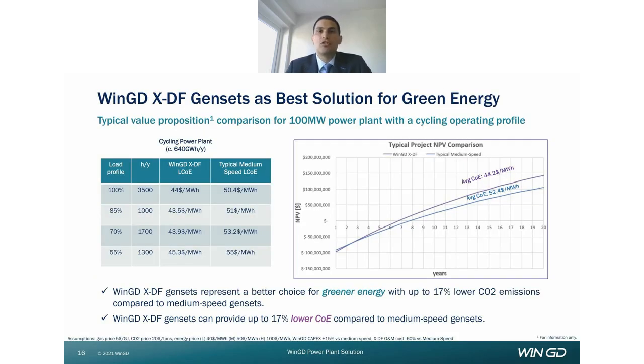I would like to conclude now my presentation with a typical value proposition, comparing 2 power plants with the same size, let's say 100 megawatt. One power plant is equipped with our XDF genset, and the similar power plant in size is equipped with a medium speed genset. The advantages that I highlighted before, the high efficiency, the low maintenance cost, the low operating cost linked to the fact that we do not need urea to control the NOx emission, are translated into a lower cost of electricity. Assuming the operating profile you see in the table on your left side, we can achieve up to 17% less cost of electricity. On average, it means $44 per megawatt hour compared to $52 per megawatt hour on average for a typical medium speed genset.